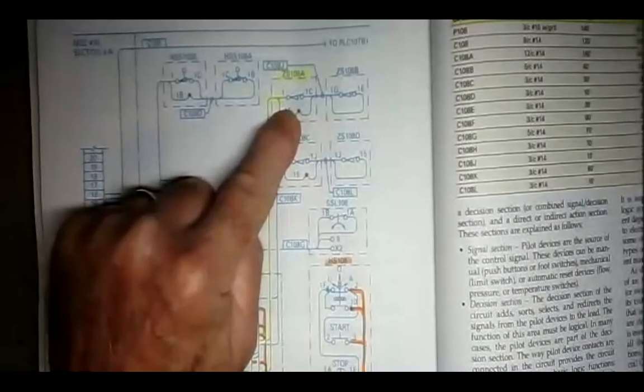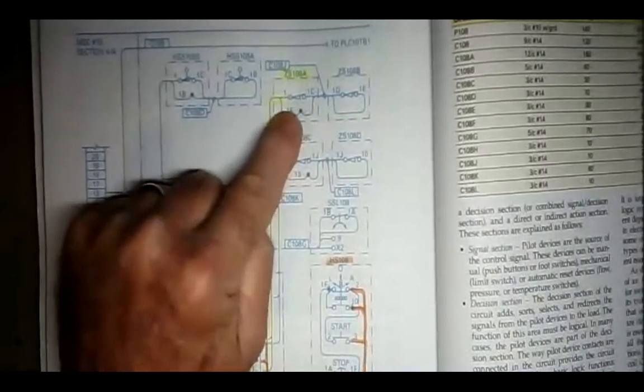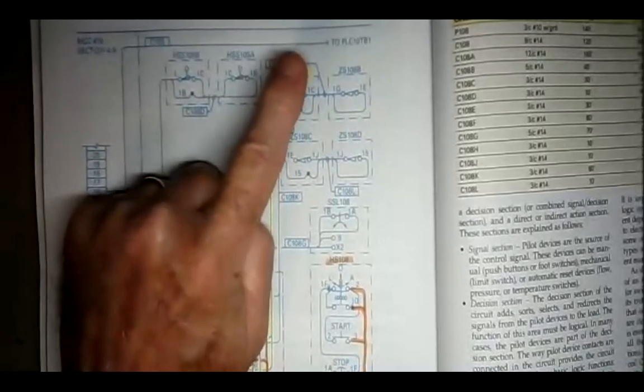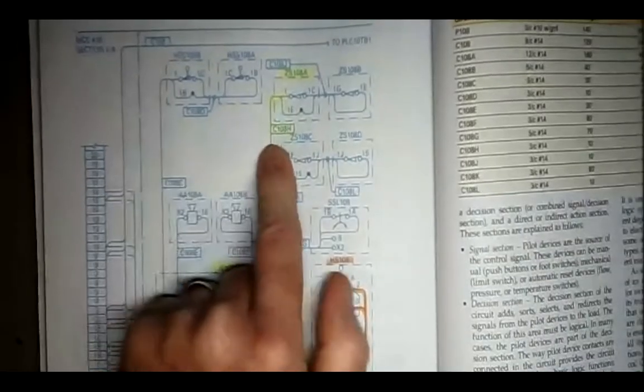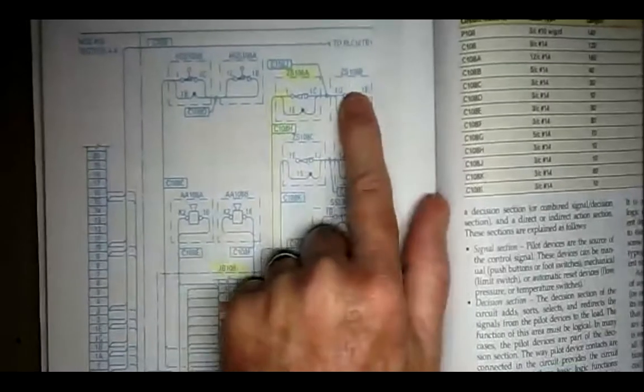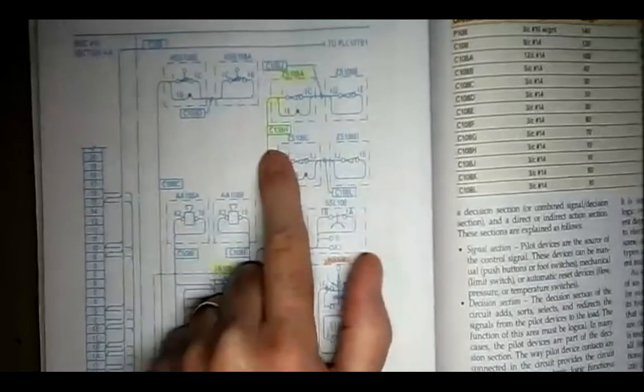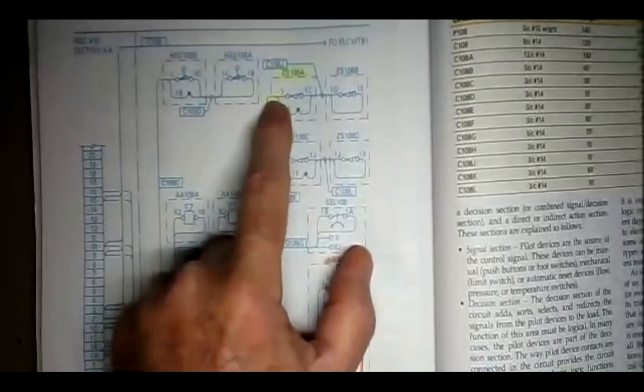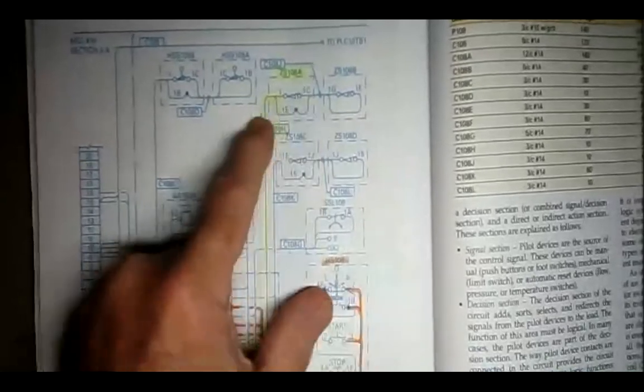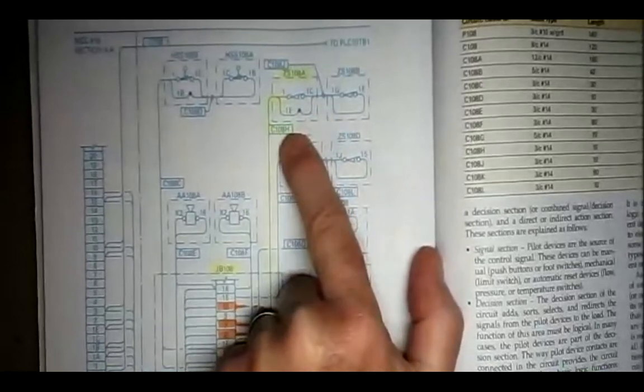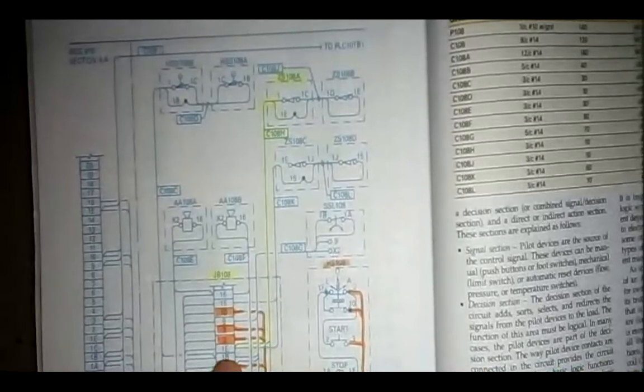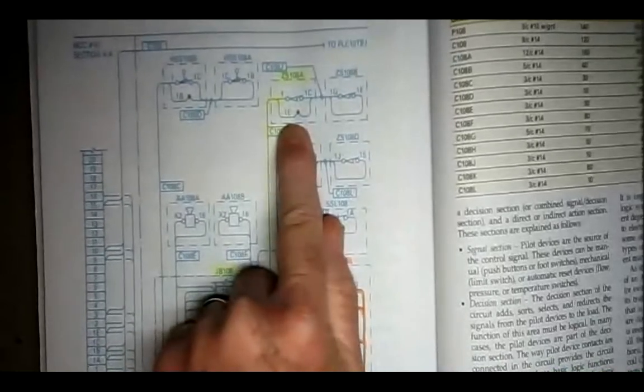here's a limit switch. This limit switch is ZS108A. That's a limit switch. And the wires coming from ZS108A are contained in cable C108H. C108J goes on to limit switch ZS108B. So H or J. C108H is the multi-conductor cable that goes to ZS108A limit switch. And we can see it's numbers 1E, and 1, no, I'm sorry, just 1 and 1E. Those are coming from this trunk line. And here's 1, and here's 1E. And those two are going up to limit switch ZS108A.